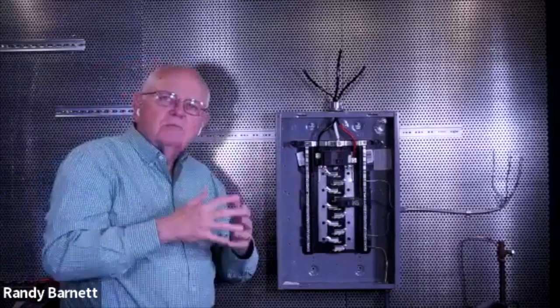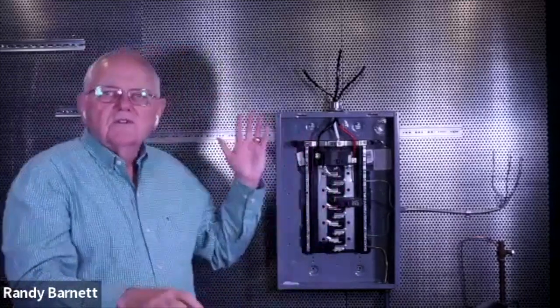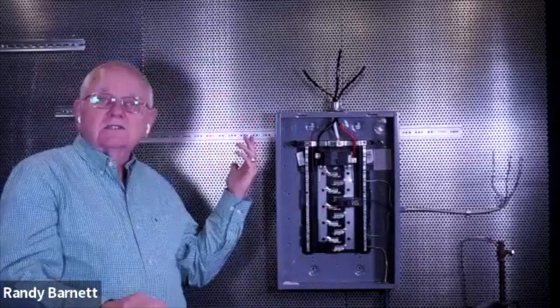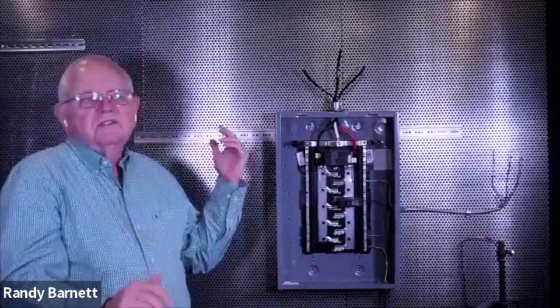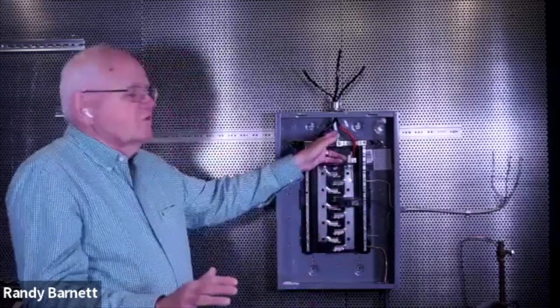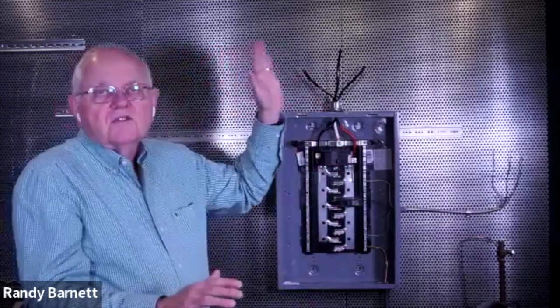Our rules are very similar, but they're a little bit different. Instead of the main bonding jumper, we have a system bonding jumper. We also have to run a supply side bonding jumper from the enclosure and that source, typically the transformer, or it could be a generator, and it's going to carry that continuity onto the enclosure where that first disconnect is going to be. So in a nutshell, that's how that works. The big difference between the separately derived system and the service is whether or not we break the neutral. If we go through a transfer switch and the neutral transfers from the utility over to the generator, then it is a separately derived system.